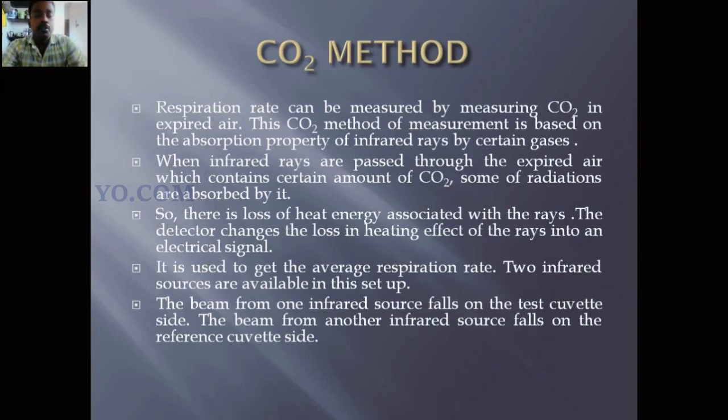So absorption means that some radiation is absorbed. Based on that property we can measure the respiration rate. When the infrared rays are passed through the expired air, which contains a certain amount of CO2, some of the radiation is absorbed by this CO2.